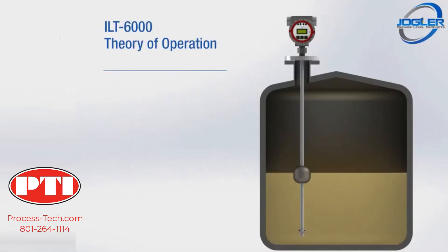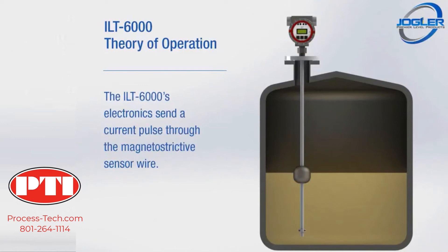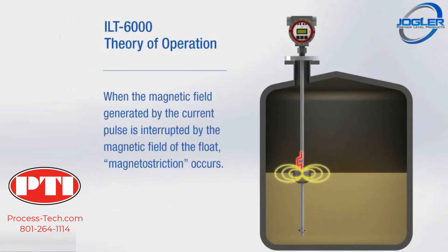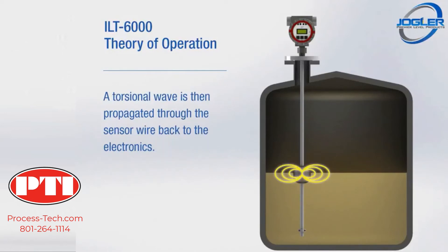The ILT-6000's electronics send a current pulse through the magnetostrictive sensor wire. When the magnetic field generated by the current pulse is interrupted by the magnetic field of the float, magnetostriction occurs. A torsional wave is then propagated through the sensor wire back to the electronics.